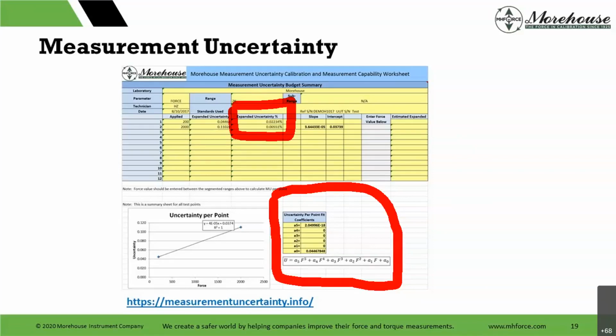That gets a little bit complicated because it's not as linear, right? When you have uncertainties that are maybe 0.02 at 10%, and then maybe your uncertainty is 0.04 at, that's going to decrease. Maybe your uncertainty is 0.01 at 50%, and then maybe it's 0.011 at 60%. Those types of things happen. And that's where there's some separate things to set the intercept and everything else.